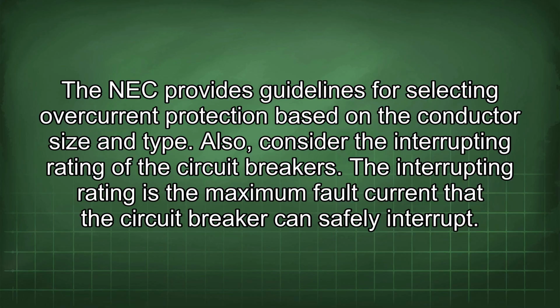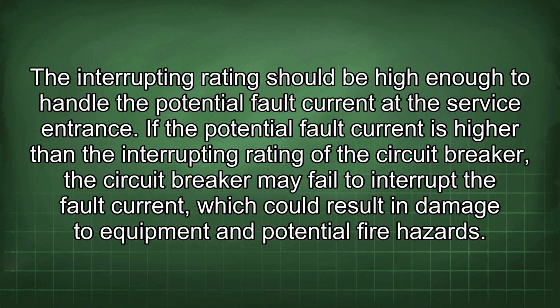Also, consider the interrupting rating of the circuit breakers. The interrupting rating is the maximum fault current that the circuit breaker can safely interrupt. The interrupting rating should be high enough to handle the potential fault current at the service entrance. If the potential fault current is higher than the interrupting rating, the circuit breaker may fail to interrupt the fault current, which could result in damage to equipment and potential fire hazards.